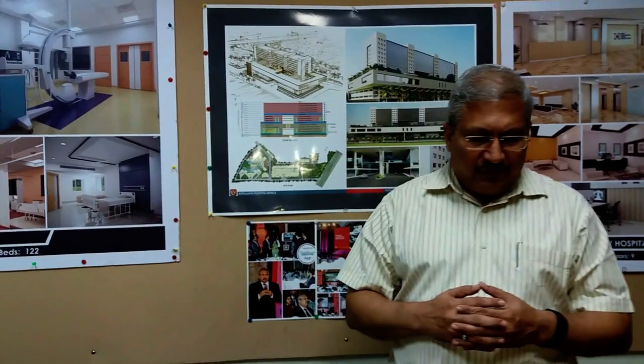The other thing which is important to understand while you're designing is if there is any phasing in the hospital, then you need to take care of that, be it vertical or horizontal, so that you need to plan now. So all your redundancies in terms of water tank capacities, space to be kept for an extra transformer, extra generators, extra chillers will need to be thought of upfront. This is very common when we design campuses of more than 500,000 square feet, 1500 beds kind of a campus.